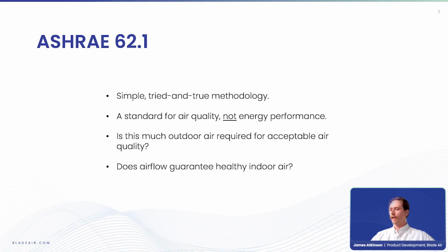There have been amendments that add correction factors for these different things. But at the end of the day, ASHRAE 62.1 was first released in 1973. There were no sensors, there was no data tracking, right? It was, I don't want to say rudimentary because at the time it was state of the art, but there wasn't as much guarantee on the end effectiveness of these systems. So it was always designed to be a very conservative estimate, right? It's a worst case scenario: dump a bunch of fresh air in there and hope for the best.